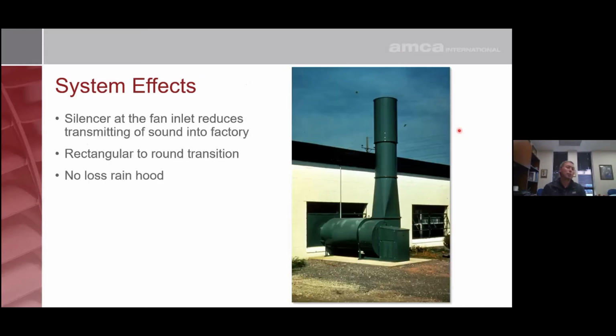Not all systems are bad. Here's actually a very good system. Here we have a fan exhausting from a facility, with a silencer on the inlet. Silencers are great because they prevent or minimize transmission of noise from the fan back into the factory. It also acts as a nice straight run of ductwork so that we don't have any losses affecting how the fan performs. Rectangular to round transition on the discharge, nicely tapered, it's not too abrupt.